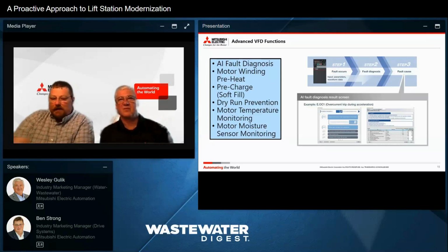Other things, the Department of Army Engineers, the Army Corps of Engineers, they're recommending for pumping stations that you have motor winding preheat, so we don't build up condensation in the motor's windings and degrade that insulation. Pre-charge, soft fill, manufacturers have different names for it, but basically we don't let the drive go into PID control until the discharge pipe is full. That prevents water hammer, huge differentials in pressure, check valve slam, those kinds of things. Dry run prevention. Again, most VFDs should have this function, and we should implement it. There's no way to tear up a pump faster than to run it dry.